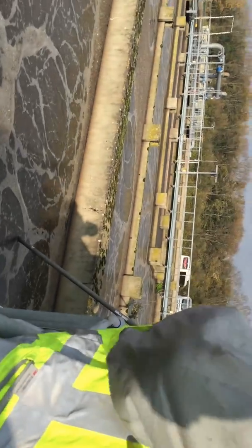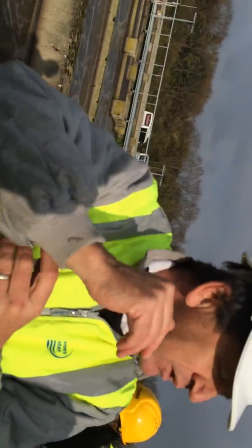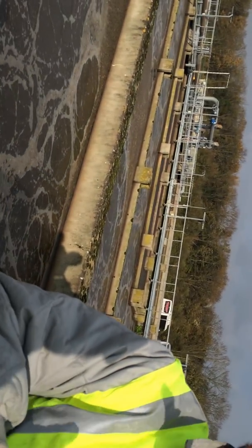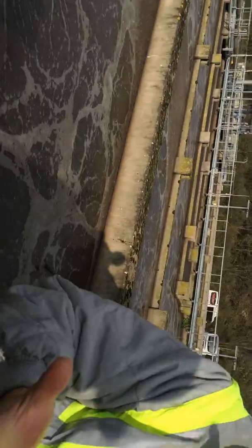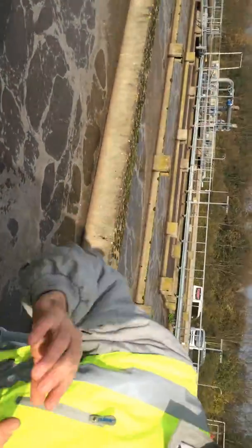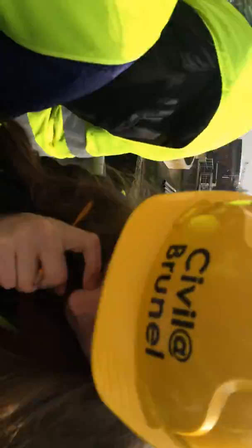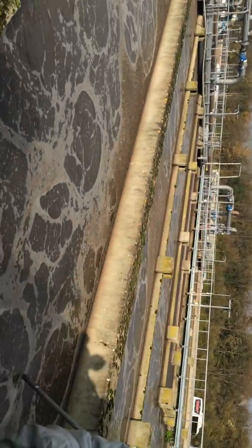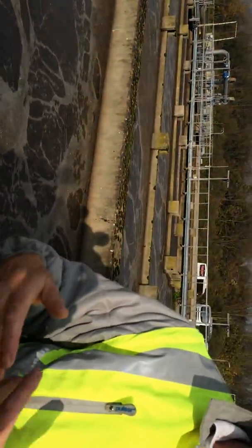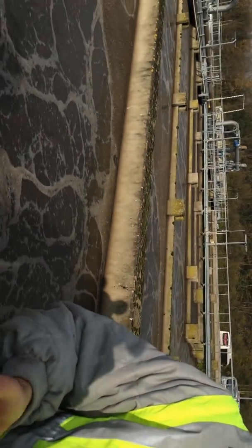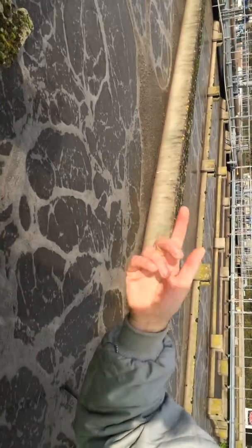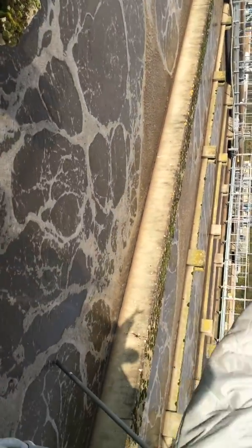So as we'll see with the final separation process, this activated sludge separates very easily from the effluent now. So in these tanks behind you, the activated sludge is settled out, and nearly all of that is returned back to the head of the process. The reason we need to do that is because the retention time in each of these tanks is probably 4 or 5 hours. Nowhere near long enough for the bacteria to grow. The slower growing bacteria we need for ammonia removal take 5 or 6 days to double. So what we have to do is keep settling the sludge out, sending it back in again.